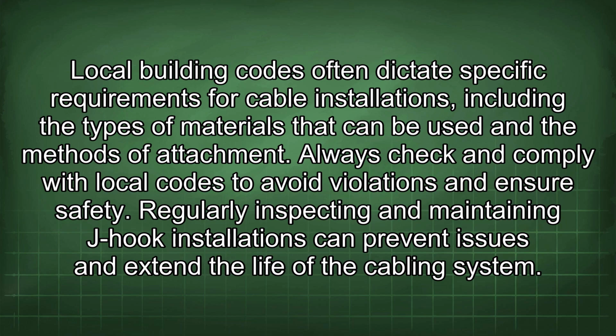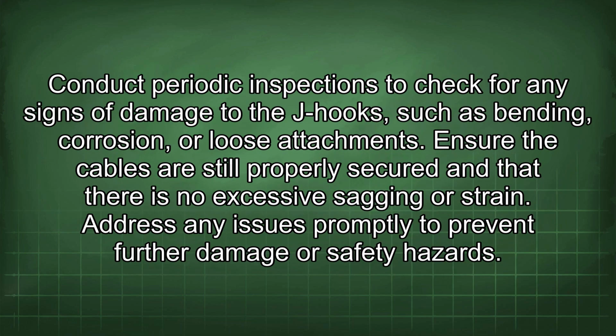Regularly inspecting and maintaining J-hook installations can prevent issues and extend the life of the cabling system. Conduct periodic inspections to check for any signs of damage to the J-hooks, such as bending, corrosion, or loose attachments. Ensure the cables are still properly secured and that there is no excessive sagging or strain. Address any issues promptly to prevent further damage or safety hazards.